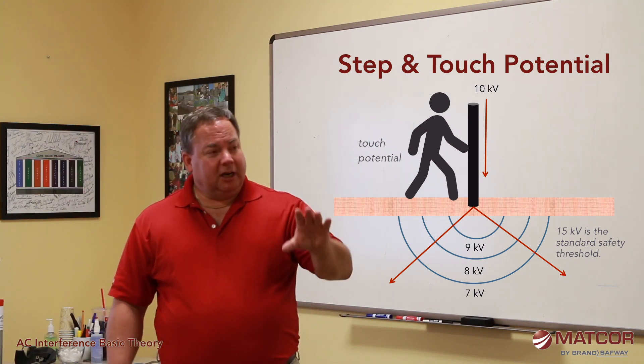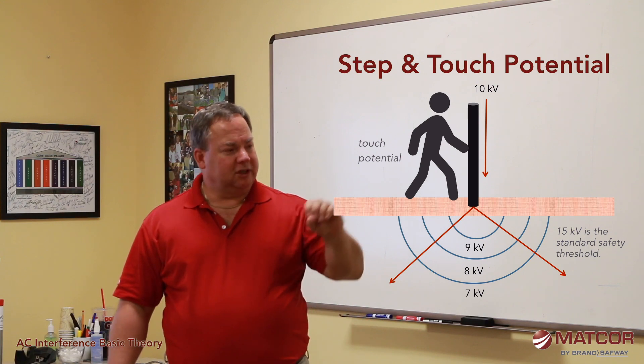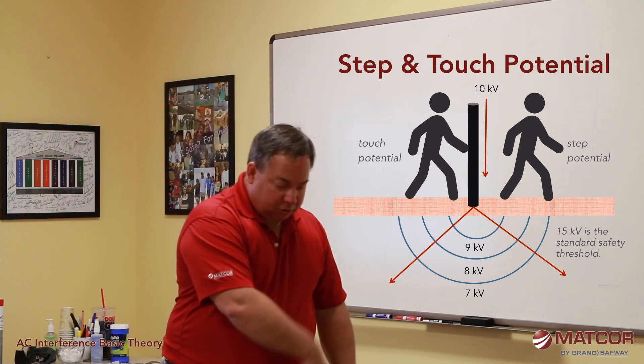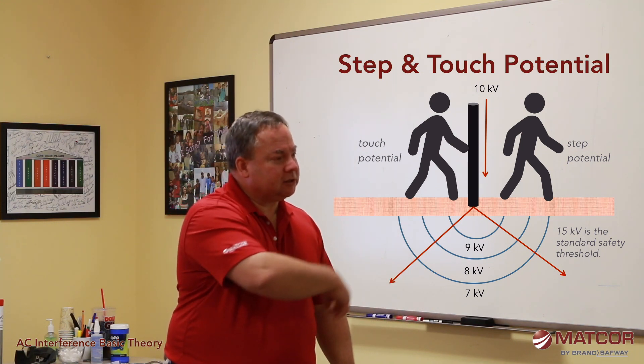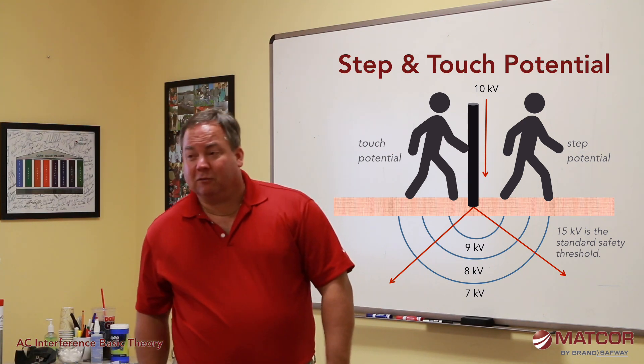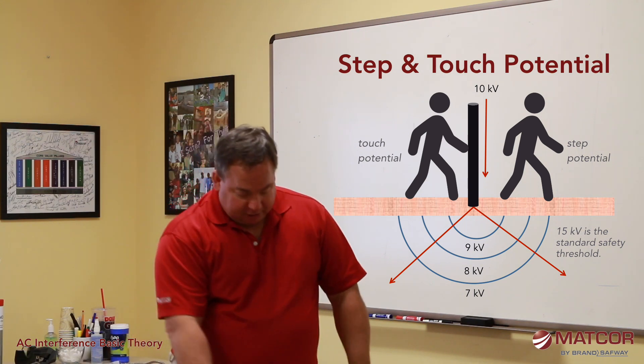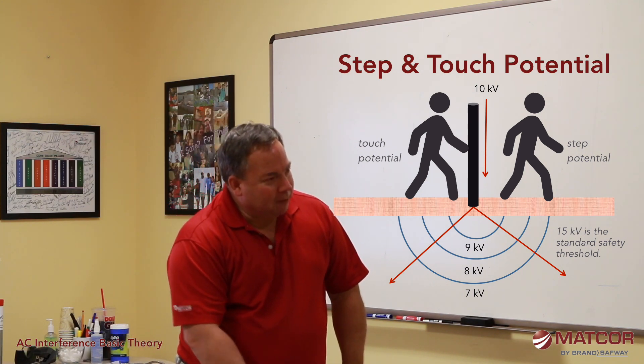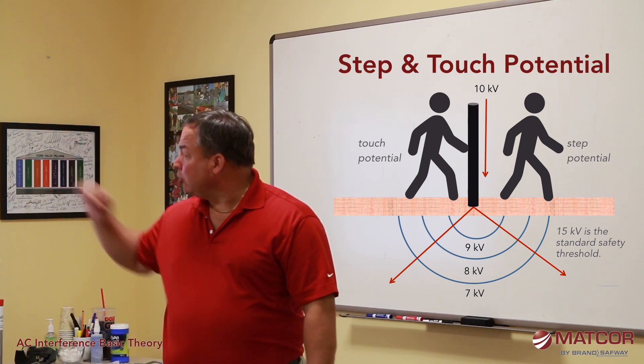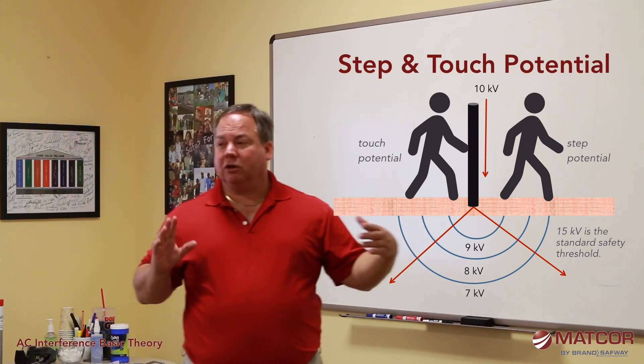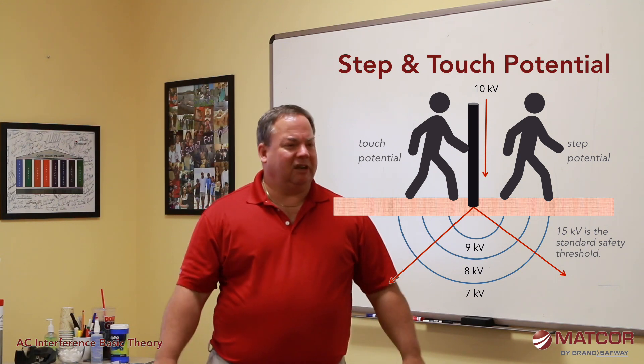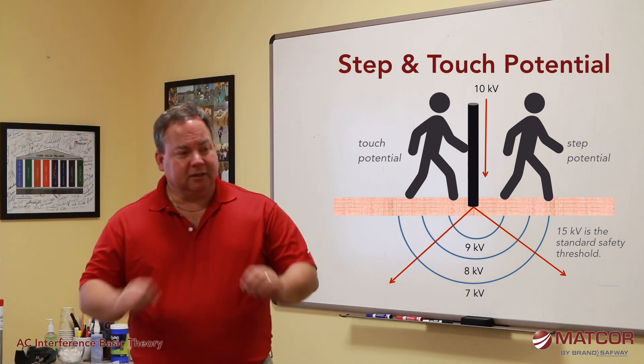So 15 volts was decided to be the maximum allowable threshold for step or touch potential. Step potential is a little different — you don't actually have to touch the device. The fact that there's a large voltage gradient around that device, and your feet are spanning that gradient, means one foot is closer to the source and one foot is further away. The voltage gradient can cause current to flow up one foot and down the other. That's called step potential — and step and touch potential is what's discussed in safety when it comes to electrical fields.